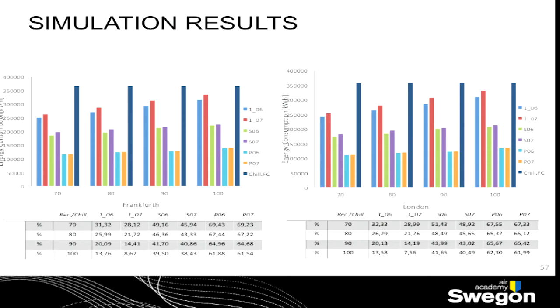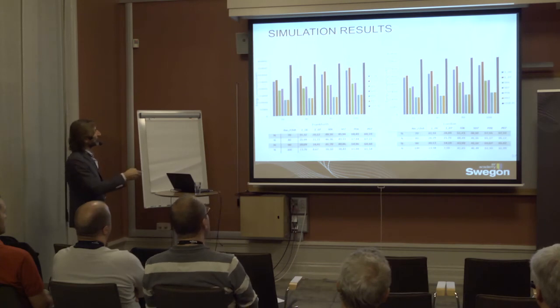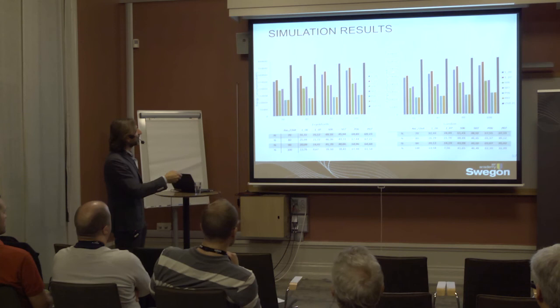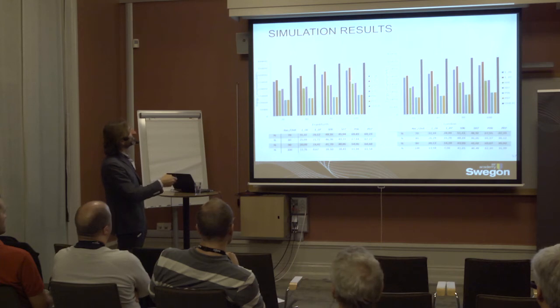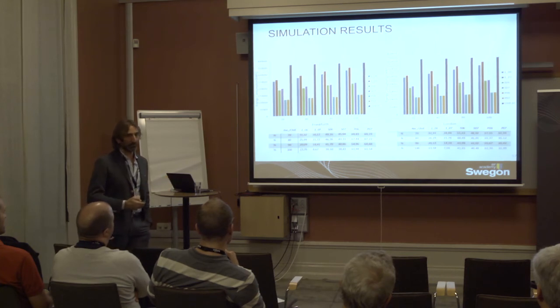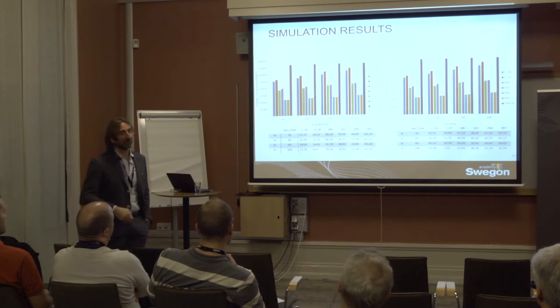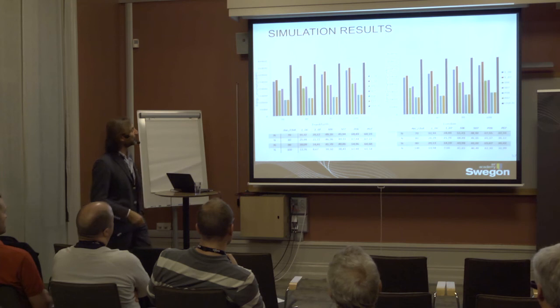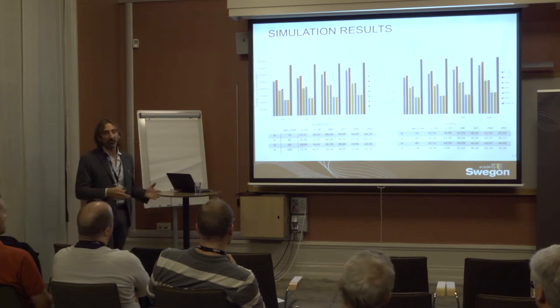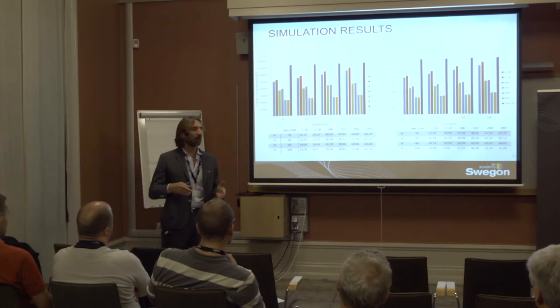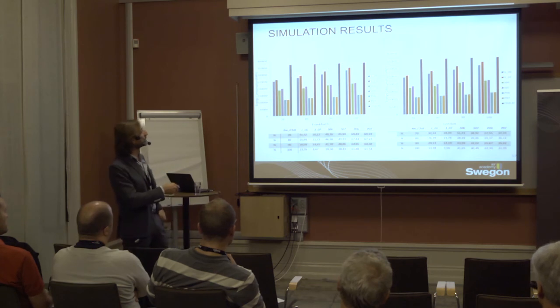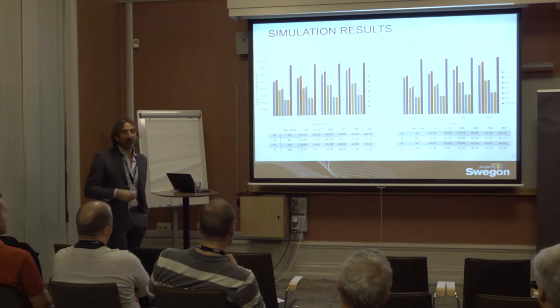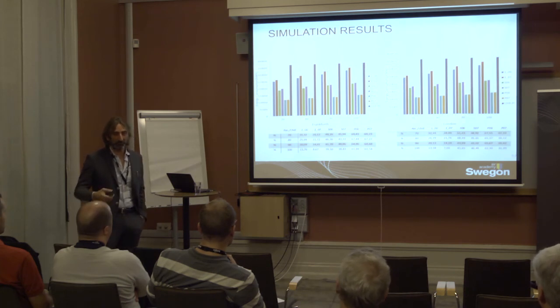So this is the energy spent by the chiller free cooling. That's always the same, of course, because it is only for comparison. And this is the energy spent to run a system with a single plate heat exchanger. So this red one with F6 filters. These are for a series of 2 plate heat exchangers, and this is with a parallel of 2 plate heat exchangers. This is due to the cutting in pressure losses due to the parallel on the outside air linked to this system. Of course, it takes to a larger unit in terms of footprint. So it is not for free, this energy recovery, let's say.